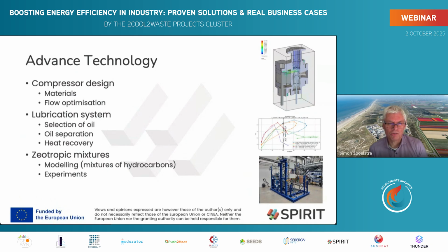The compressor technology used most of the time is piston and screw compressors. They use oil as lubrication, and at high temperatures this oil can be an issue, so we've done studies on how to select the oil given your heat pump conditions. We also made a paper out of this.